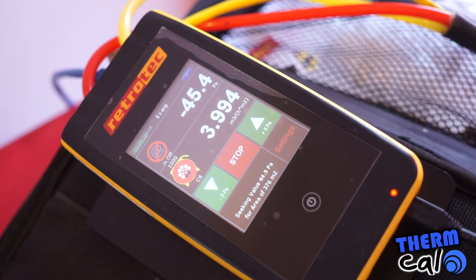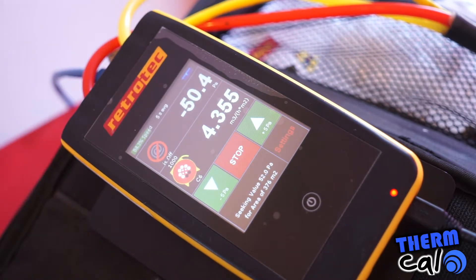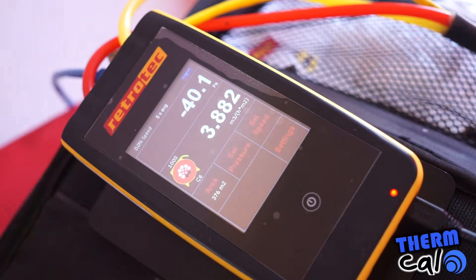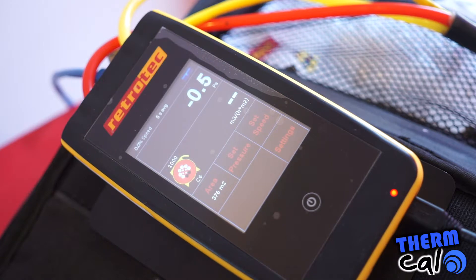50 pascals is the pressure at which the airtightness result is given to the developer or homeowner. It's expressed in metres cubed per hour of airflow through the building, divided by the metre squared of the envelope of the building — that's the total walls, floors, roof and ceilings.